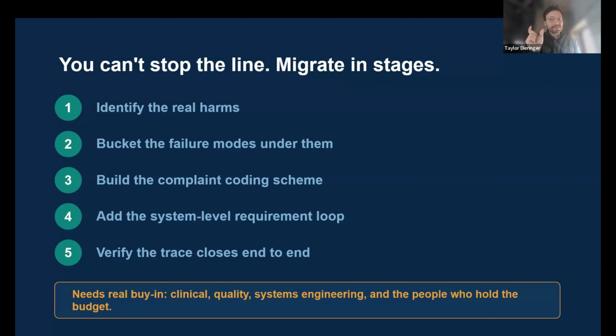Like I said, creating those two individual buckets, hazardous situation harm pairs. Everyone usually has failure mode effect analyses. So now my next step is to take all of those individual sequences of events and attribute them to the correct buckets. Again, from that previous slide, building that complaint coding scheme, so having that translation tool to get from complaint to our hazard analysis. And then the fun part, we touched on this at a very high level, but essentially what we also want to do is use our systems engineering as an entryway into our evidence pathway, and then use a trace matrix to close the loop from our evidence all the way into our FMEAs.